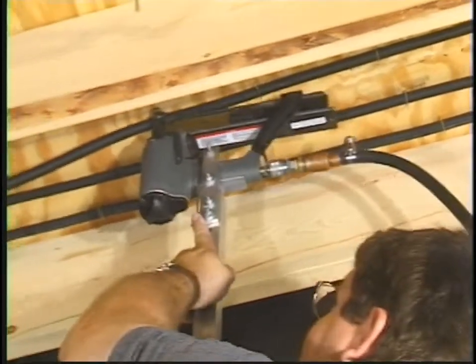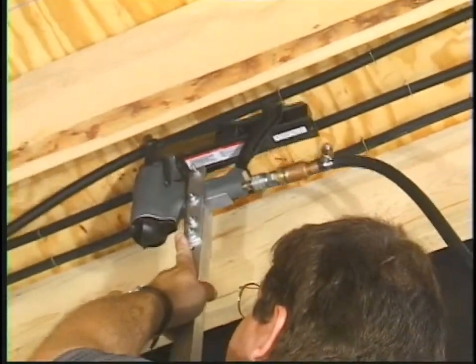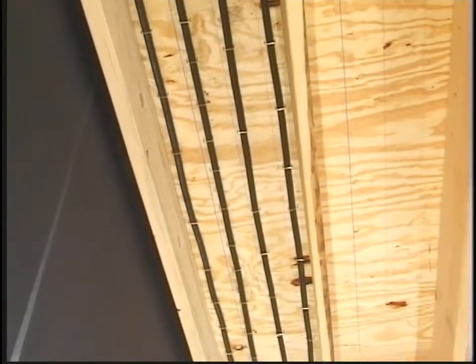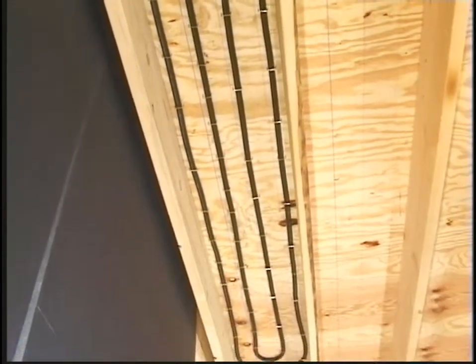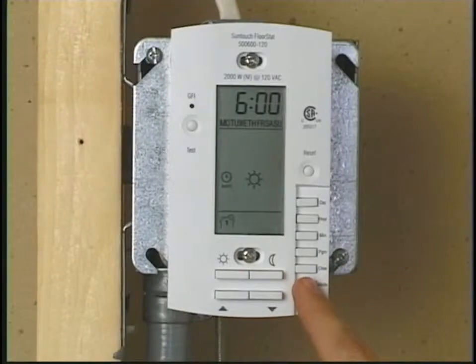And these radiant floor systems pump heated water from a boiler through polyethylene tubing laid underneath the floor. The temperature in each room is controlled by regulating the flow of hot water through the tubing loop. This is done by a system of zoning valves or pumps and thermostats. Although ceramic tile is the most common floor covering for radiant floor heating, almost any floor covering can be used.